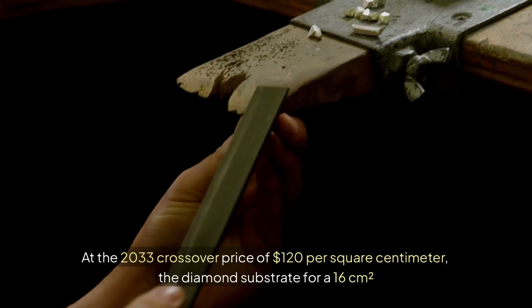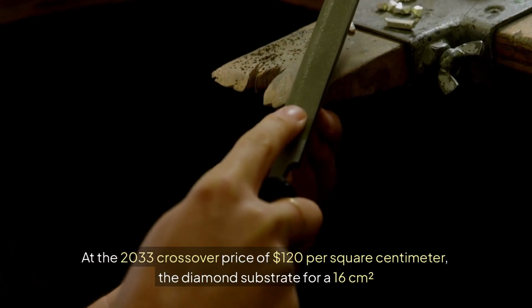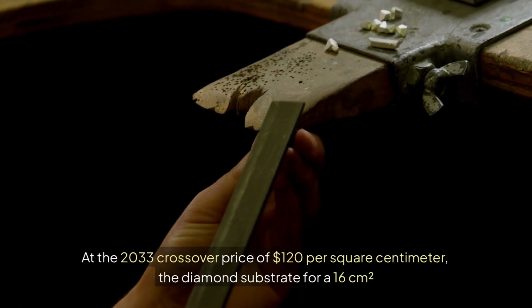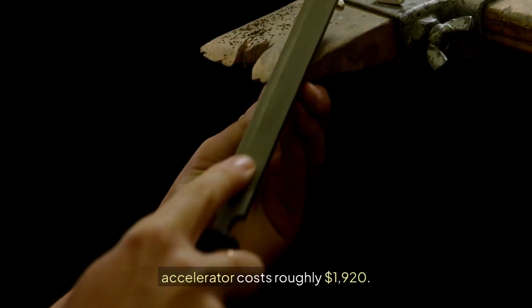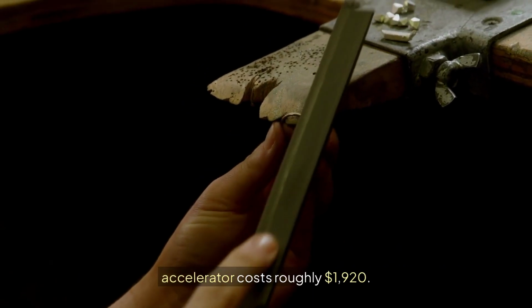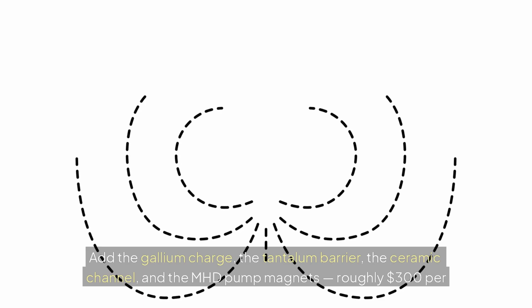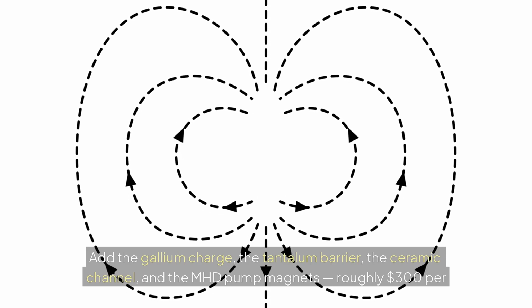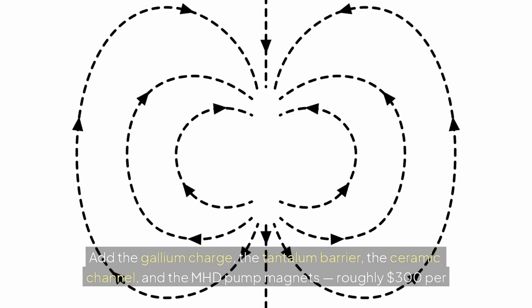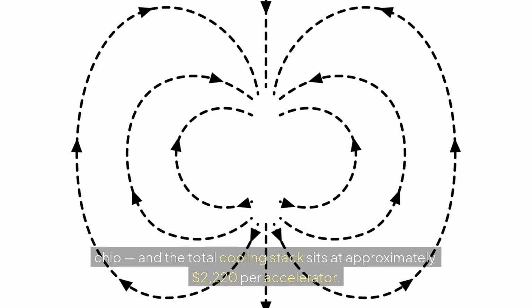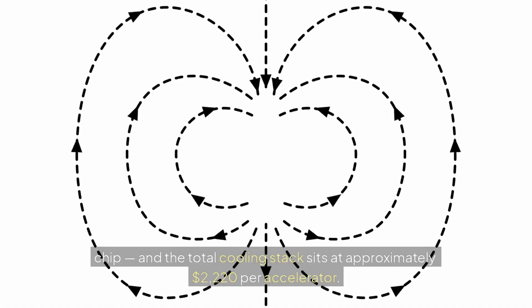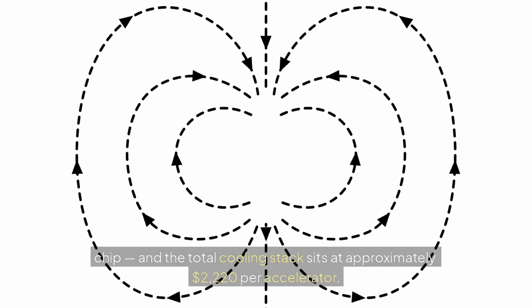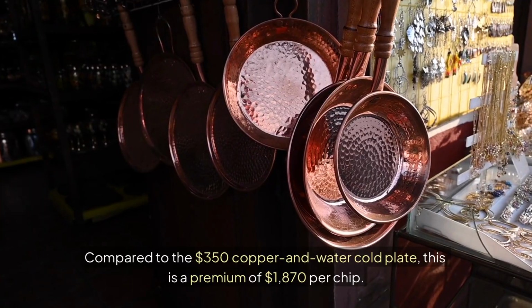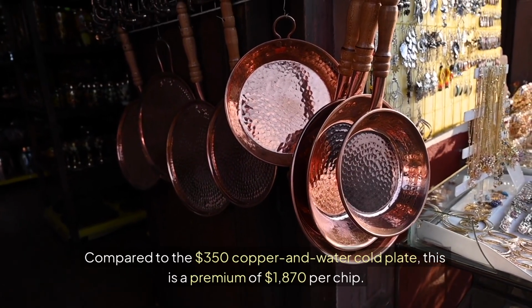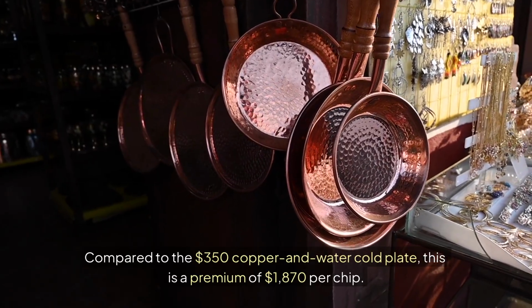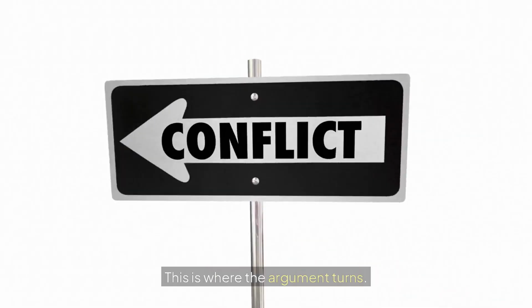At the 2033 crossover price of $120 per square centimeter, the diamond substrate for a 16 cm² accelerator costs roughly $1,920. Add the gallium charge, the tantalum barrier, the ceramic channel, and the MHD pump magnets, roughly $300 per chip, and the total cooling stack sits at approximately $2,220 per accelerator. Compared to the $350 copper and water cold plate, this is a premium of $1,870 per chip. This is where the argument turns.